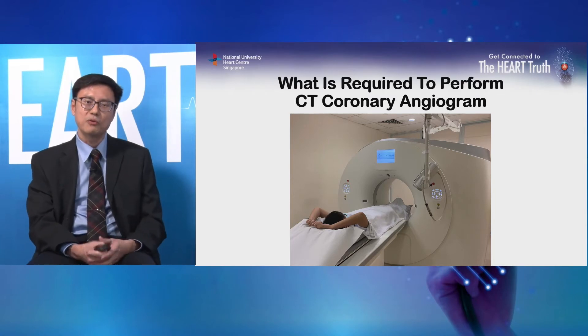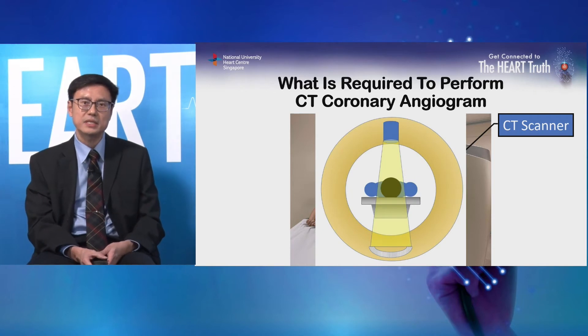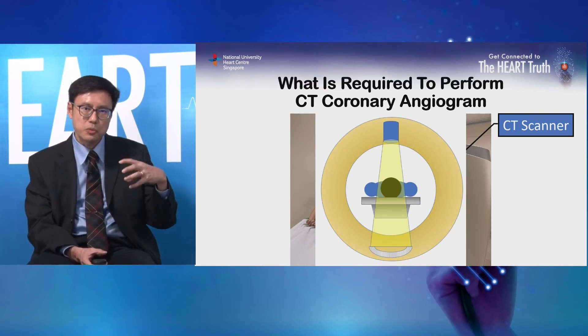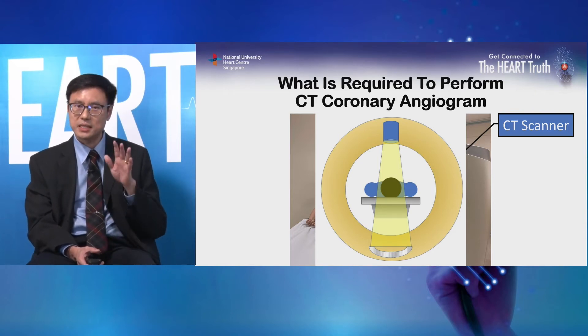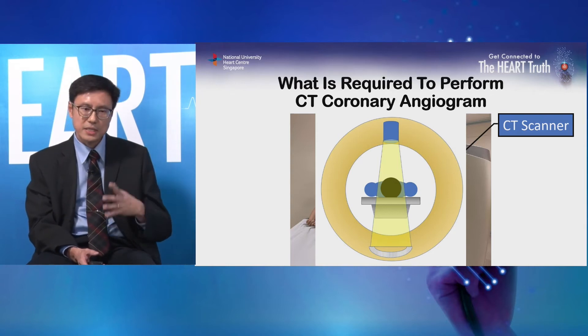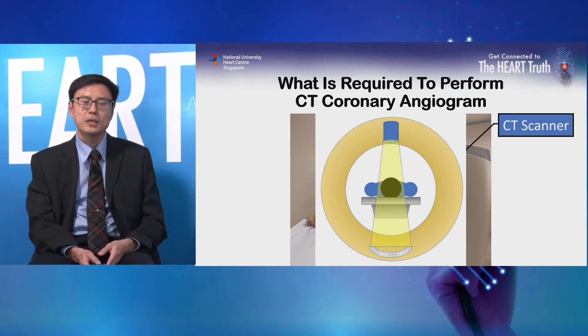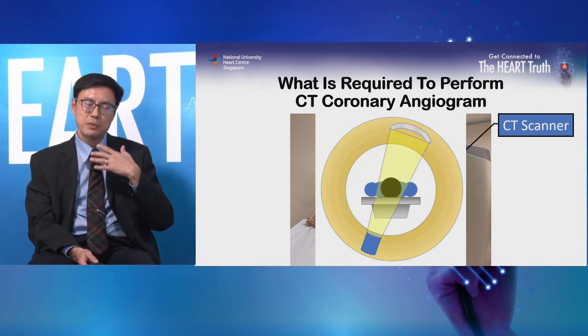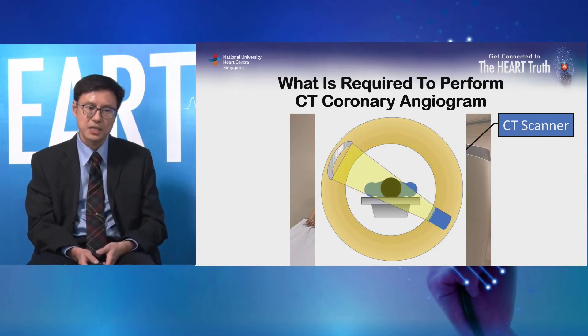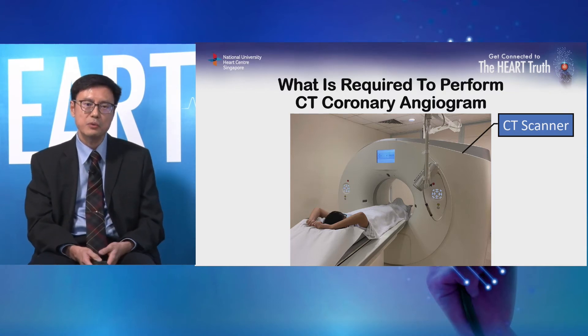For CT coronary angiogram, we need the scanner. The CT scanner is essentially an x-ray tube that sends x-rays through the body of the patient, who lies in the center of the scanner. These x-rays are detected by an array of detectors opposite the x-ray tube. As the body passes through the gantry, the tube rotates to take pictures of the region of interest — in our case, the heart. This is then processed by computers to give us the images we require.